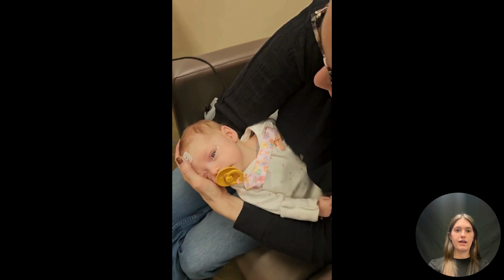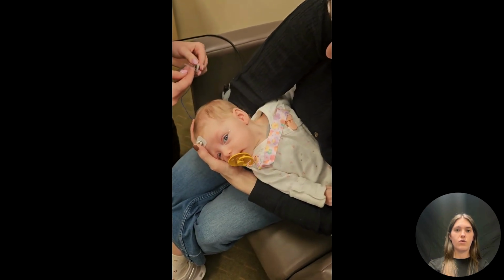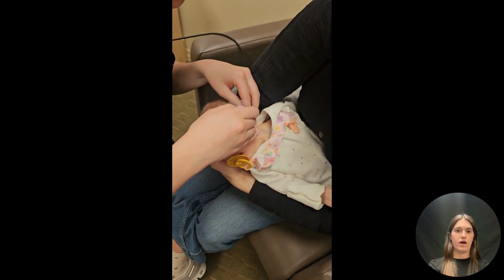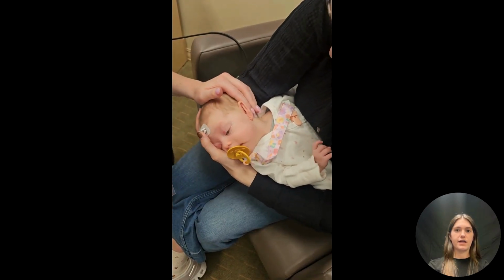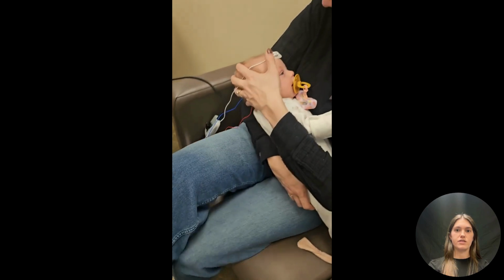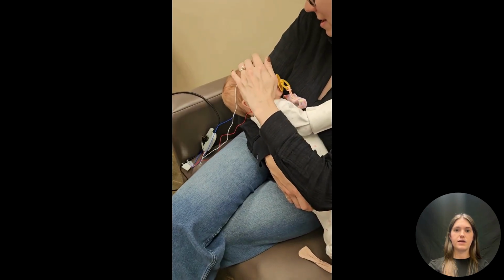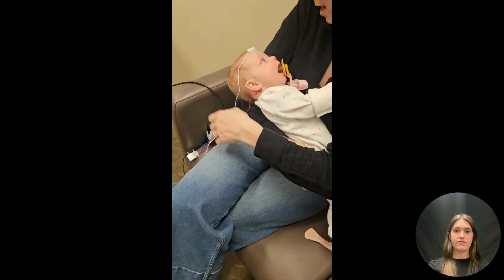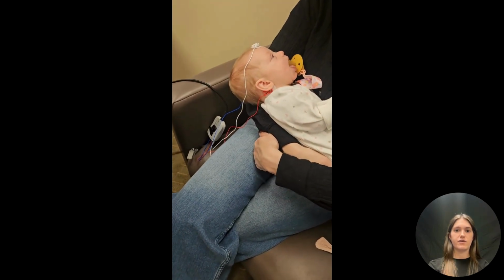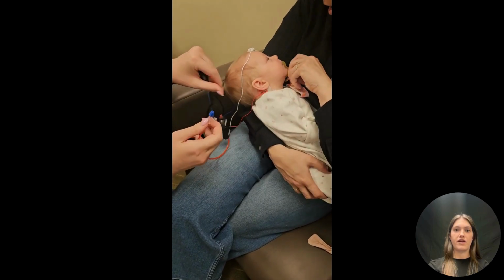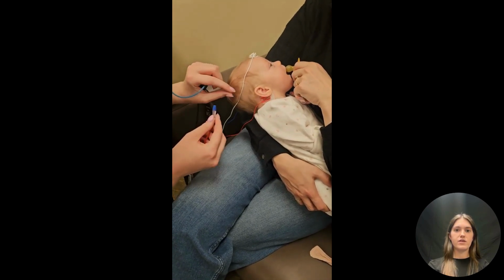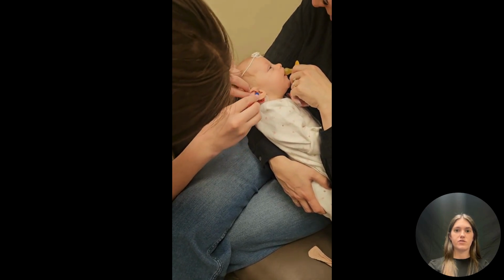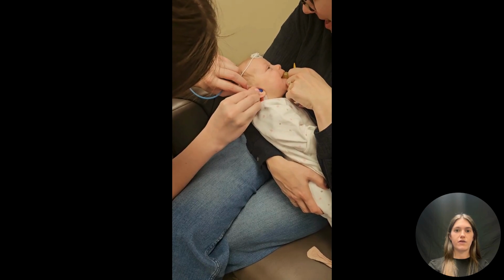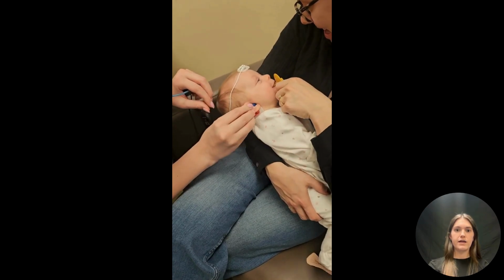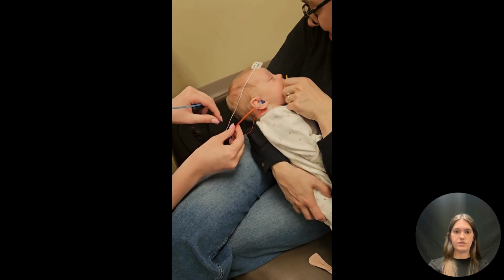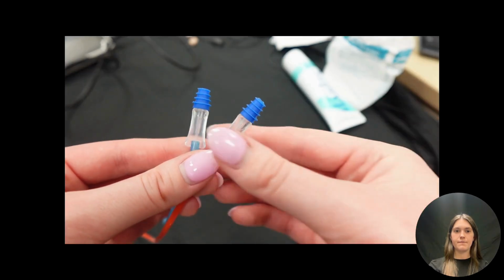Electrodes can't be touching anything except the baby's skin, so holding them in place during the screening will not work. Simple things like skin and debris can interfere with the electrode's ability to record ABR responses. Impedance, or resistance to the flow of energy, can be easily checked for each electrode with most ABR screening equipment. Reference the equipment manual for your specific ABR screening system for instructions on how to check electrode impedances and for the recommended impedance values that are optimal for screenings.